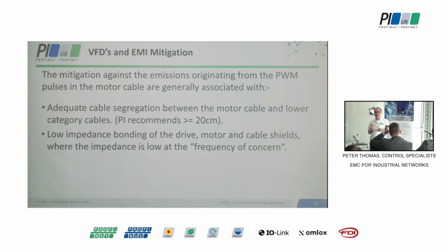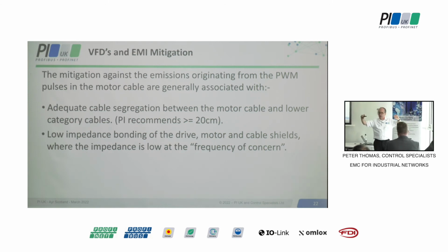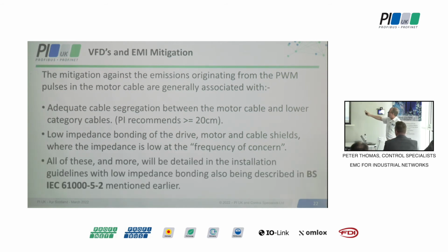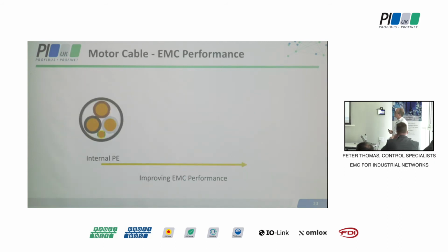One of the standards has long since said that star earthing, where you might have two distinct panels with an earth bar, with two long cables going to a main earth terminal, is good for electrical safety and bad for EMC at all frequencies. So it's in the document for you. All of these and more will be detailed in the installation guidelines, with low impedance bonding and all of the consequences of that being detailed in 61000-5-2.